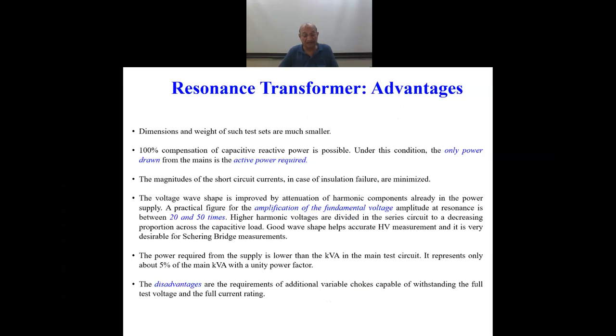I mean, if we didn't have unity power factor, if we hadn't compensated the capacitive reactive power, you would have needed much higher voltage to be applied at the primary of the test transformer, which reduces at unity power factor to the tune of only 5%. This is a very big added advantage of compensating the capacitive reactance. There's only one disadvantage: the requirement of additional variable chokes capable of withstanding the full test voltage and the full current rating.